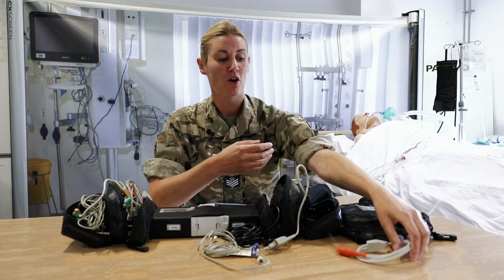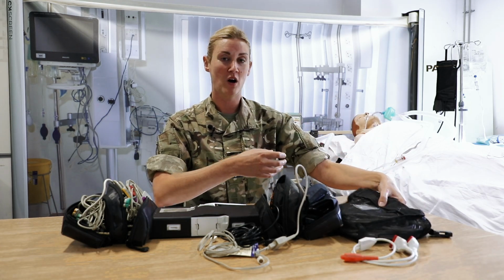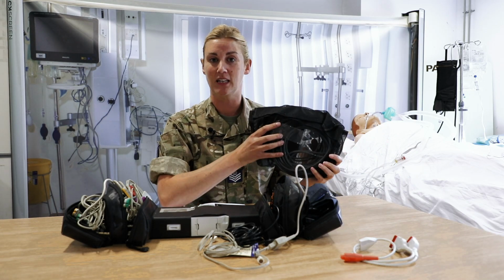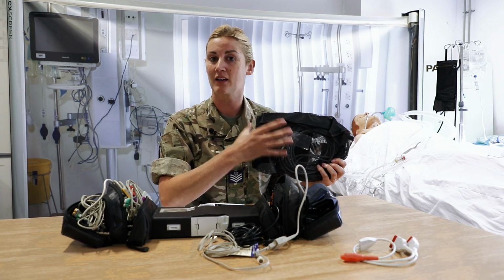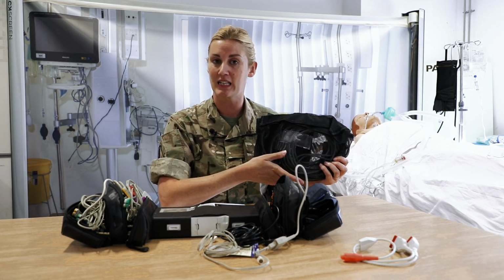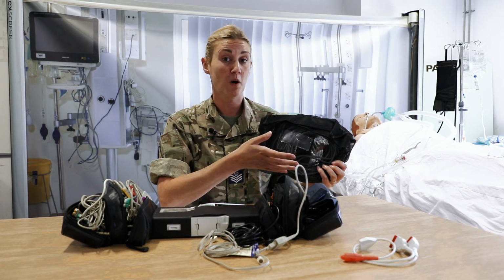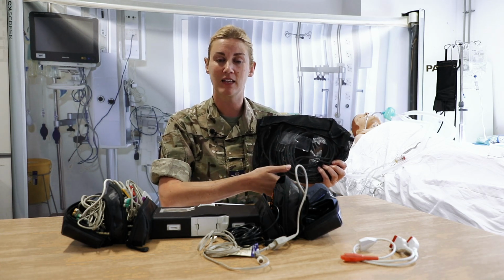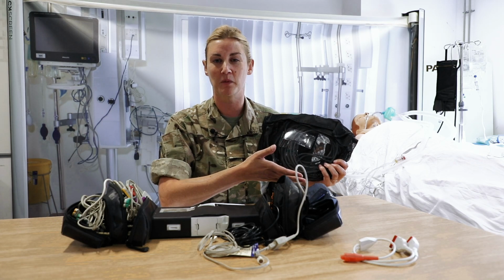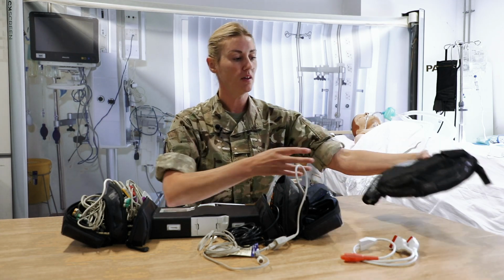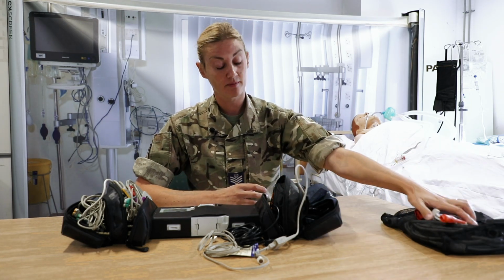While you're there, while you've remembered that you've got those, it's worth also checking your invasive leads. So take these out of the bag and confirm that you've got as many invasive leads as you require. The Corpuls can monitor up to 4 invasive leads, but most of the time we're only going to be monitoring 3. So make sure you've got it all.